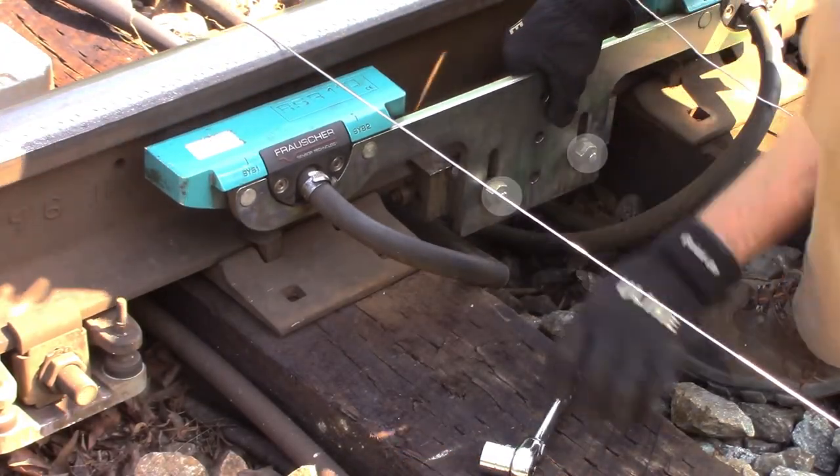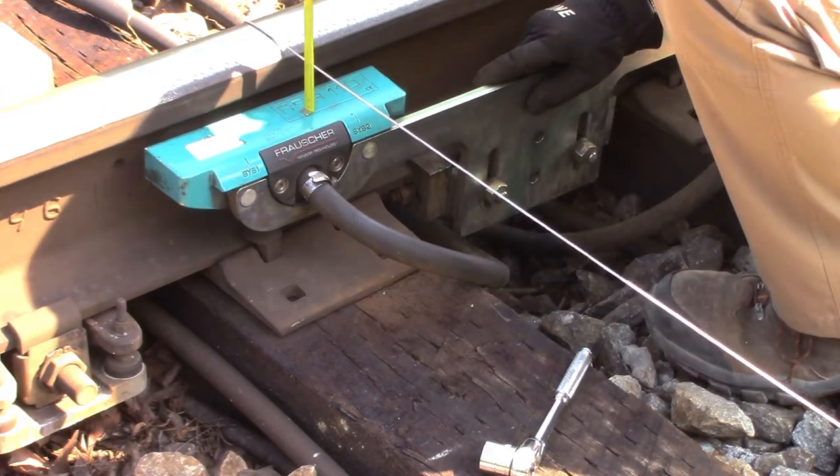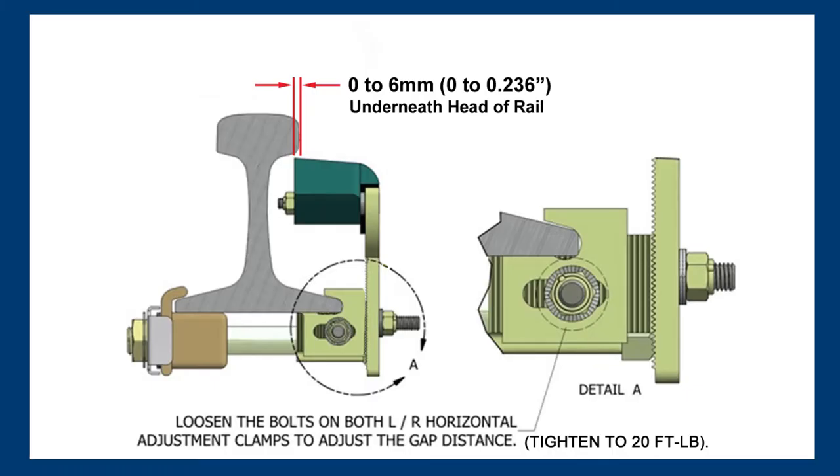Loosen the two nuts on the front plate to make vertical adjustments, then tighten to 20 foot-pounds to secure. When viewed from above, the inside edge of the Frauscher sensor should extend from 0 to 6 millimeters underneath the head of the rail. To make horizontal adjustments, loosen the two nuts securing the horizontal adjustment clamp, then tighten to 20 foot-pounds to secure.